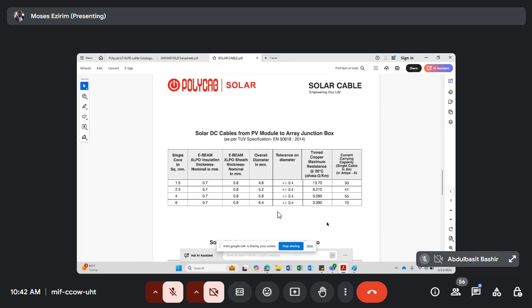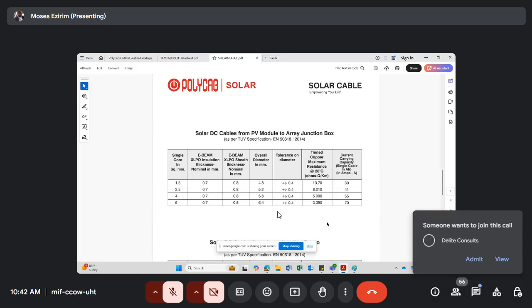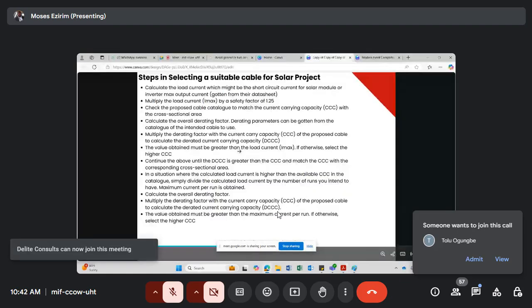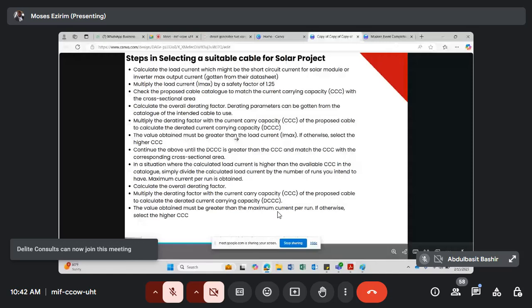The cable's current carrying capacity should be greater than the required current carrying capacity, and you match it with the corresponding cross-sectional area. You can see that I've gotten 55, which is the current carrying capacity, and I'm matching it with the corresponding cross-sectional area, which is 4 mm. Do you understand that?